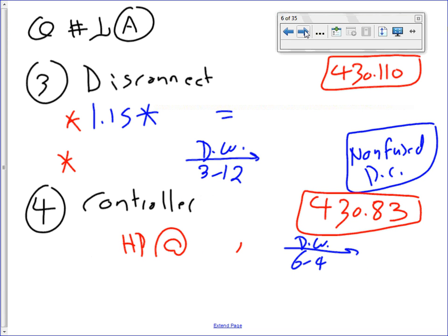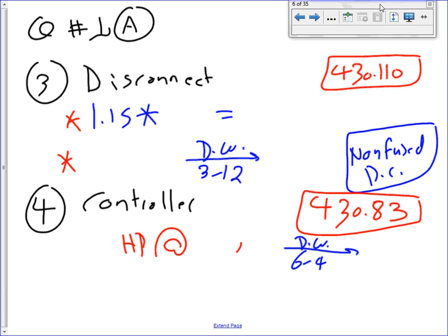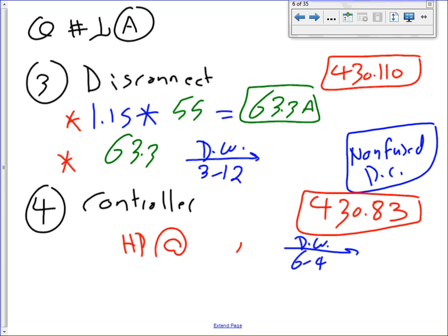Okay, now let's go to the disconnect. The disconnects, gentlemen, the code book very clearly said, oh, by the way, use 1.15. Where do you get the 1.15, guys? You get it from 430.110. So you take 55, multiply here, that will get you 63.3 amps. And then you take the 63.3 amps, take it to the table, like we have done before, that will get you a 100 amp disconnect. 100 amp disconnect.